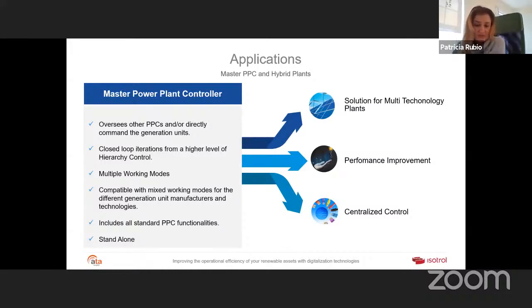So our master PPC was implemented to directly control the two conflicting phases and the two conflicting PPCs, managing an incoming automated set point without adding more than 30 to 40 milliseconds to the control loop. So in a grid code that was extremely strict in voltage time response, the master PPC was able to identify the side with most inertia and compensate. It was able to adjust automatic corrections in real time to evenly distribute the power set points. It was able to provide this response as a single wind farm, which was ultimately what was requested by the grid code.